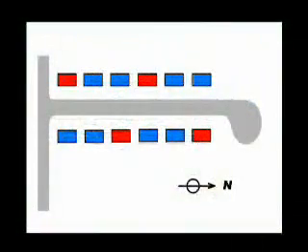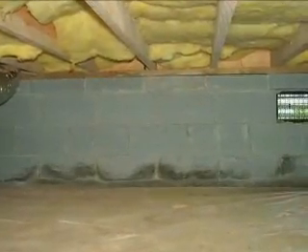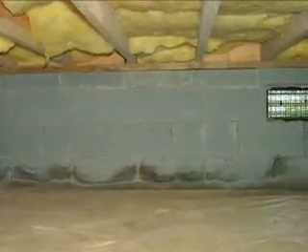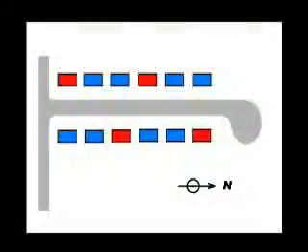The 4 homes in red on the site plan are the control group of wall-vented crawlspaces. The control group has open foundation vents and a carefully installed 6 mil poly vapor retarder that covers the entire earth floor. The remaining 8 homes in blue are the experiment group of closed crawlspaces.